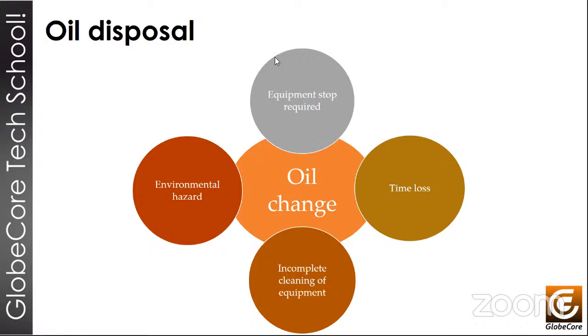So an oil change process just generates waste oil. It wastes our time. It's also a process that doesn't achieve any long-term results. This is probably the most important part. And when we talk specifically about the equipment that we offer as regeneration solutions, you will see how regeneration actually helps to clean out the transformer to remove the contaminants that are trapped inside the solid insulation paper. Right, so let's go to the next slide now.